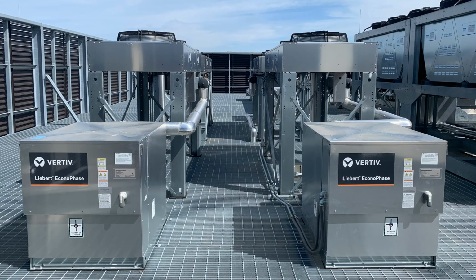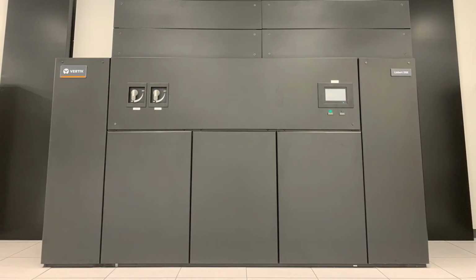We utilize a DX-based cooling system because it eliminates water in the data halls and it's very energy efficient in the Kansas City climate. The system is modular, which limits the effect on the cold air delivery in case of a condenser failure. The data halls are configured with CRAC units along the outer edges of the room. The CRAC units are powered by a primary and secondary power feed, which are both backed up by generators.